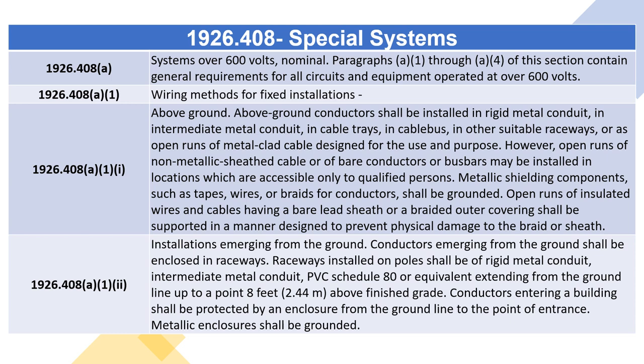1926.408(A)(1): Wiring Methods for Fixed Installations. 1926.408(A)(1)(i) — Above Ground. Above-ground conductors shall be installed in rigid metal conduit, in intermediate metal conduit, in cable trays, in cable bus, in other suitable raceways, or as open runs of metal-clad cable designed for the use and purpose. However, open runs of non-metallic sheathed cable or of bare conductors or busbars may be installed in locations which are accessible only to qualified persons.